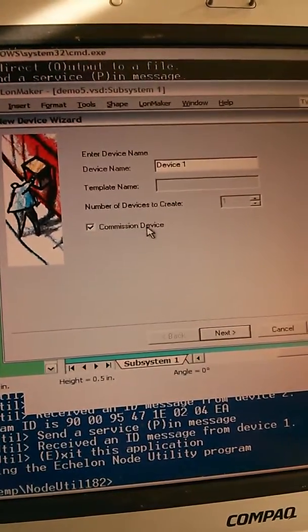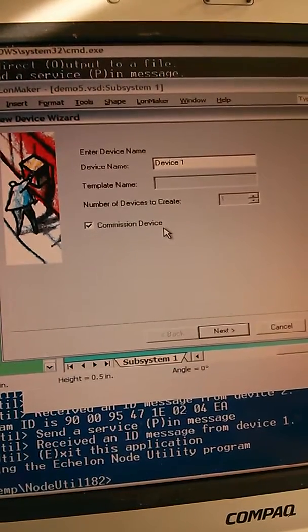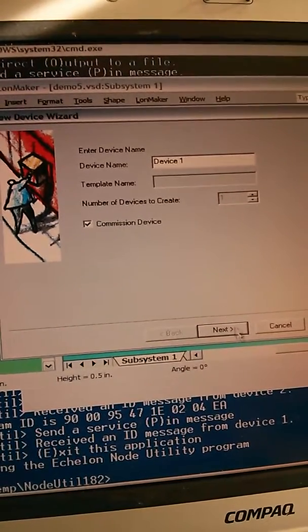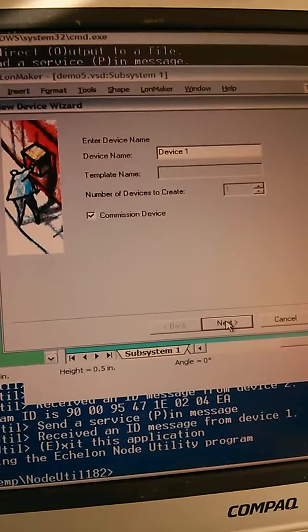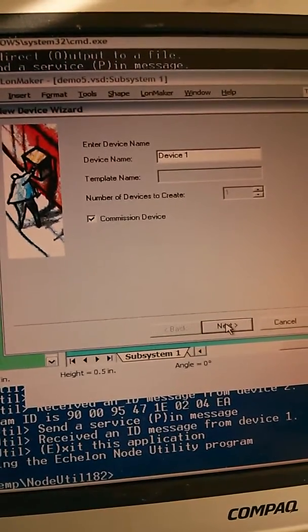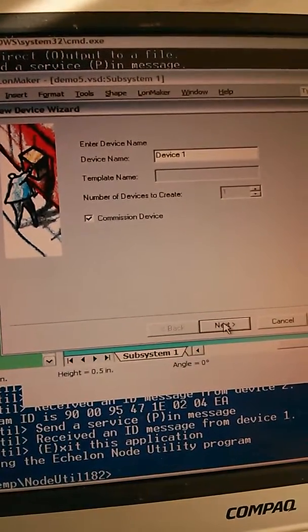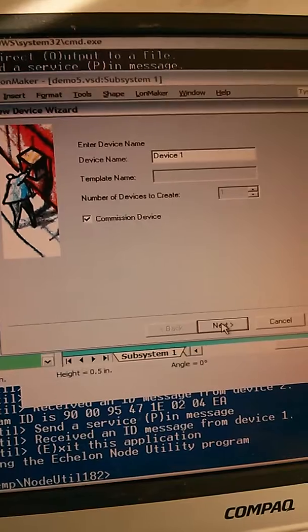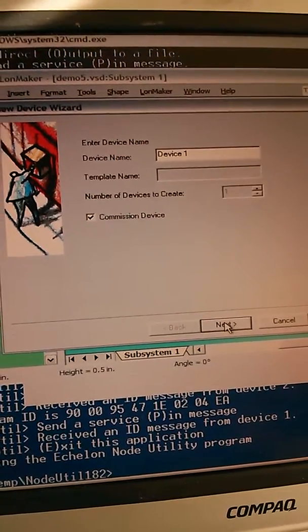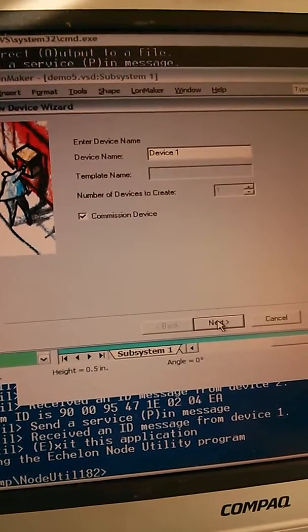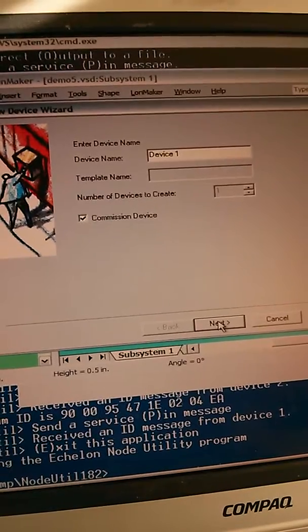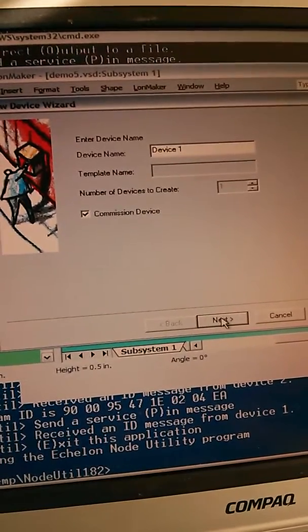An address in LonWorks consists of a domain, a subnet, and a node ID. Until a device is commissioned, it doesn't have an address, and it cannot be addressed or referenced or communicated with by another LonWorks device, except by using what they call network management functions, but I'm not talking about those today.